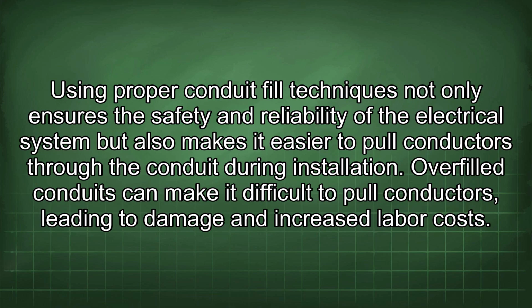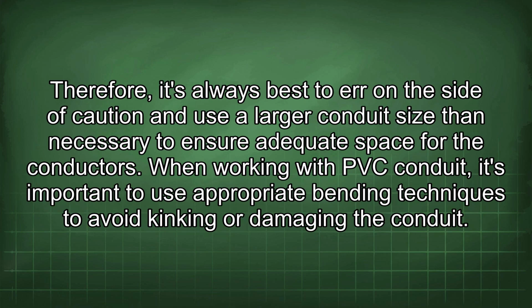Using proper conduit fill techniques not only ensures the safety and reliability of the electrical system, but also makes it easier to pull conductors through the conduit during installation. Overfilled conduits can make it difficult to pull conductors, leading to damage and increased labor costs. Therefore, it's always best to err on the side of caution and use a larger conduit size than necessary to ensure adequate space for the conductors.